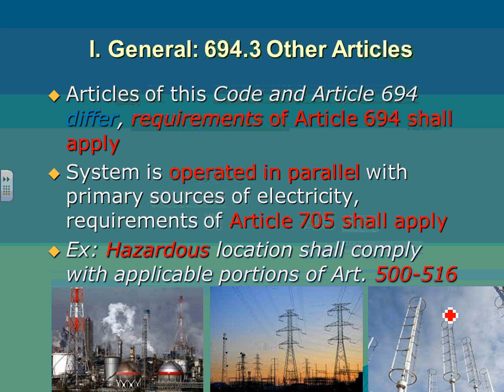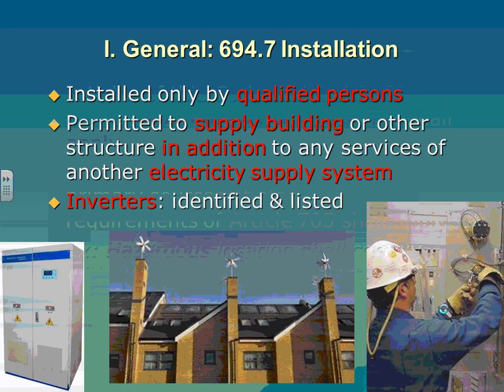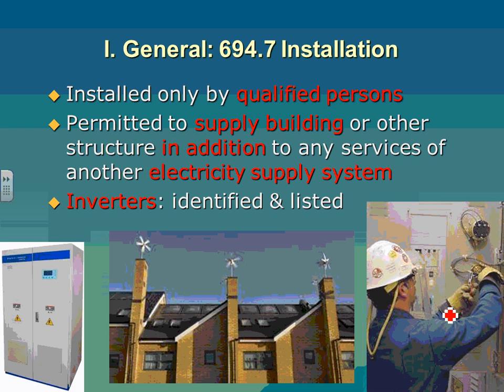And if you decided to go explosion proof, you're familiar with hazardous locations, right? All the electricians and engineers here. If you decided to put this wind turbine in a hazardous location, Class 1 Div 1 or Class 1 Div 2, Class 2 Div 1 or 2, then you have to adhere to the rules of the hazardous location. That means explosion proof and a bunch of other things. Well, who would go and put an alternator right in a Class 1 Div 1 location, so you can have an explosion-proof alternator or explosion-proof inverter converter? So anyway, these are just things I'd like to throw out for them.